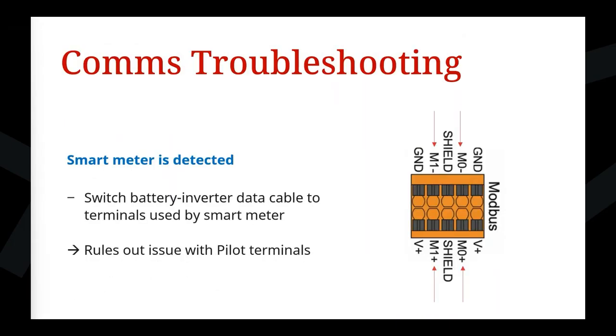If you have a situation where, say, the smart meter is being detected but the battery is not being detected, one thing you can do, which can rule out an issue with the pilot terminals, is switch between the Modbus 0 and Modbus 1 terminals, M0 and M1, on the orange communication plug. Take the smart meter connection off the one it currently uses and connect it to the battery, and then you can see if it's working or not. That way you'd know if it's an issue with the terminals on the pilot itself or some other issue.